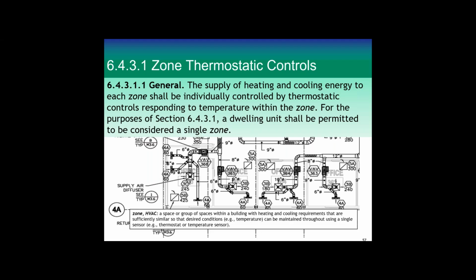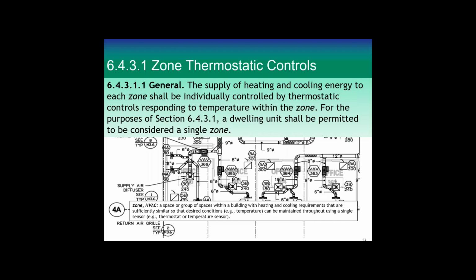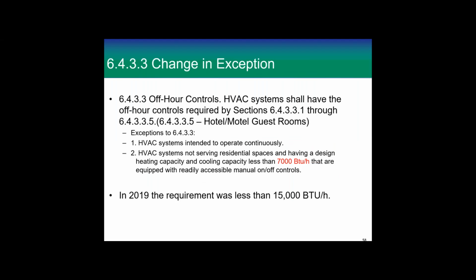Now, the problem is that a zone is a space or group of spaces within a building with heating and cooling requirements that are sufficiently similar so that the desired conditions, normally temperature with a thermostat, can be maintained throughout using a single sensor. So if this VAV box has a thermostat, then that room's probably in good shape. But maybe the one up here, maybe the one down there, if this thermostat's not in the right place, and this area is not running with the same occupancy type and that sort of thing, then people put the thermostat in the wrong place, or they try to put too many areas on the same box, and then it's not sufficiently similar so that the desired conditions can be maintained. That's when you get hot calls and cold calls, that sort of thing.